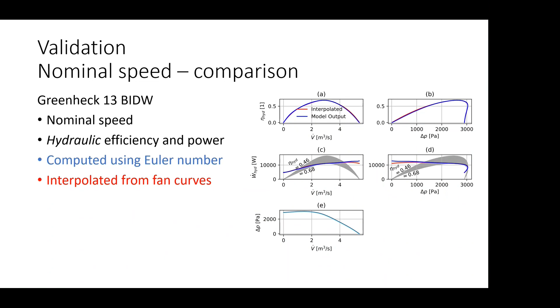We also plotted a few lines representing what would happen if we assumed constant efficiency. The lower line, at 0.68, is the peak hydraulic efficiency of this fan—if we always assumed peak efficiency, we'd always underestimate power consumption. Assuming a smaller value, 0.46, roughly two-thirds of peak efficiency, leads to underestimation in some regions and overestimation in others, similar to what we showed at the beginning of the presentation: underestimating power at low flow rates and overestimating at higher speeds.